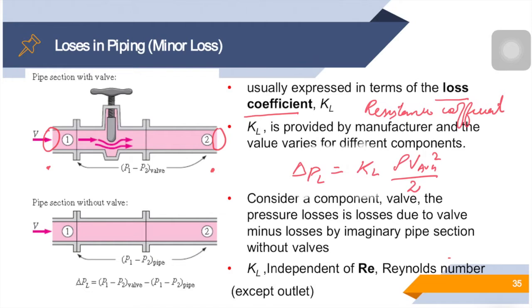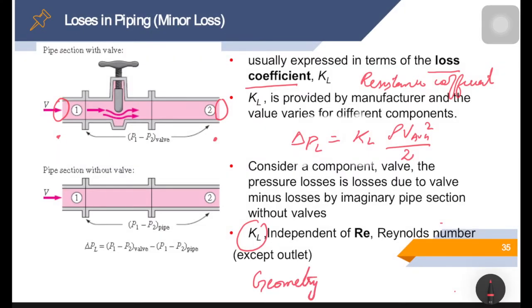So the pressure loss delta PL equals KL times rho V-average squared over 2. We need to note that KL is independent of Reynolds number, though in general the loss coefficient depends on geometry. A sharp bend will have a higher loss coefficient than a smooth elbow. While KL does depend on both geometry and Reynolds number, it is usually assumed to be independent of Reynolds number, which is a reasonable approximation since most flows occur at very large Reynolds numbers.